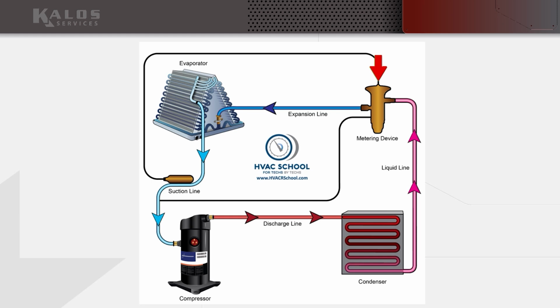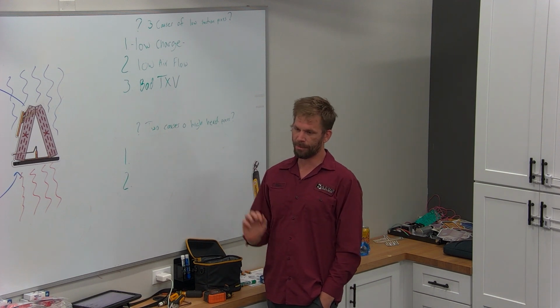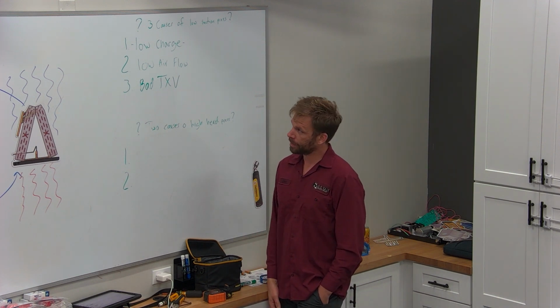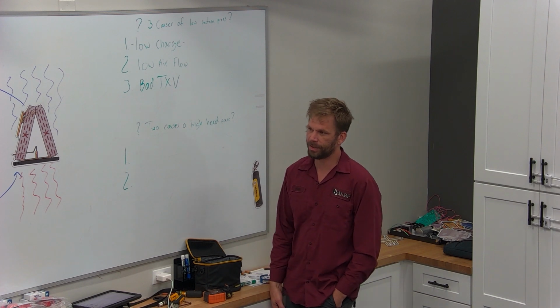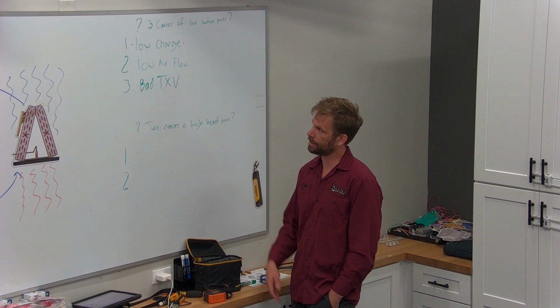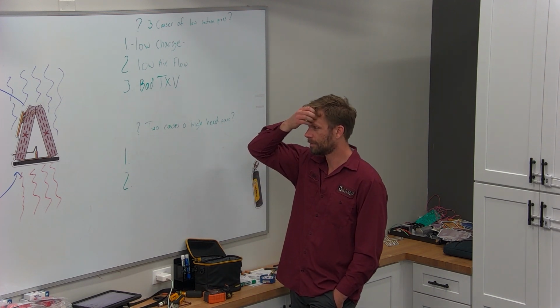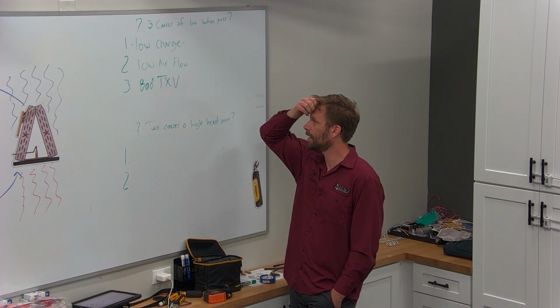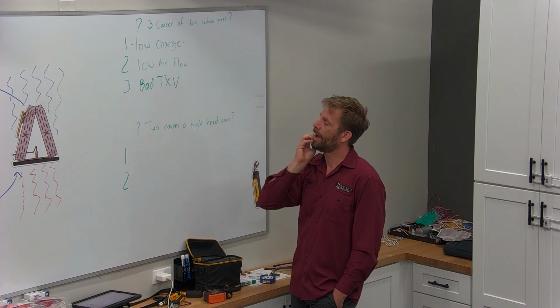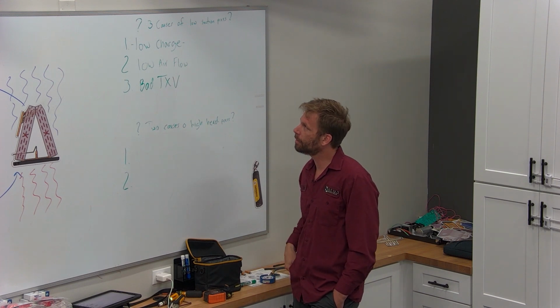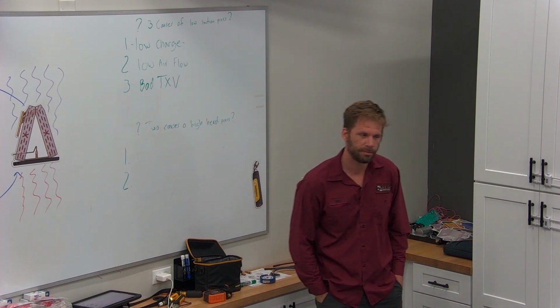The TXV is located in the liquid line, so sometimes people just call that a liquid line restriction. However, 9 out of 10 times it is the TXV when it is a restriction in the liquid line. So we're going to just call this a bad TXV. How does a TXV create low suction pressure?